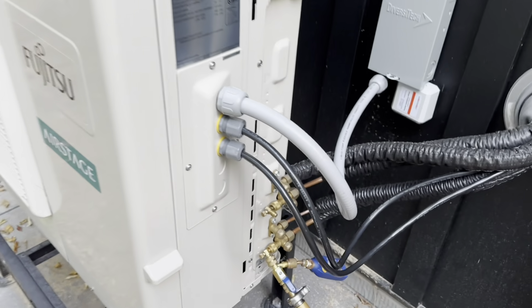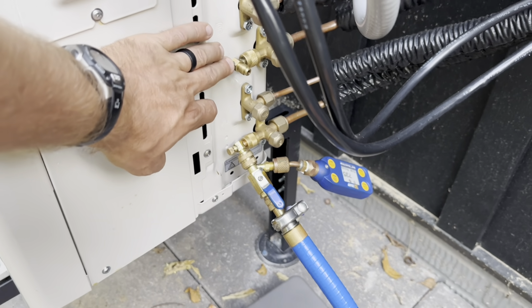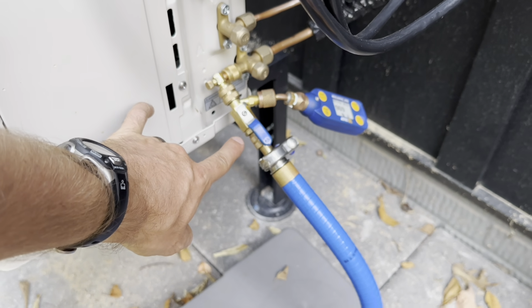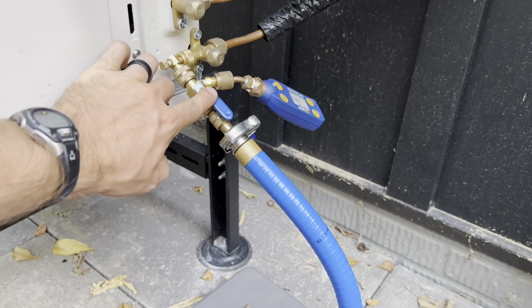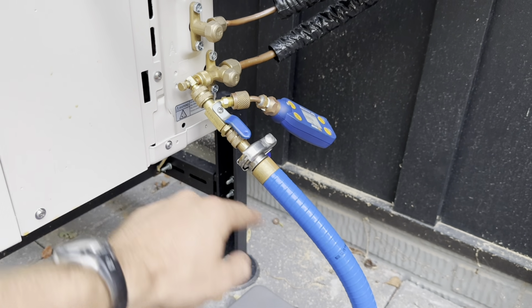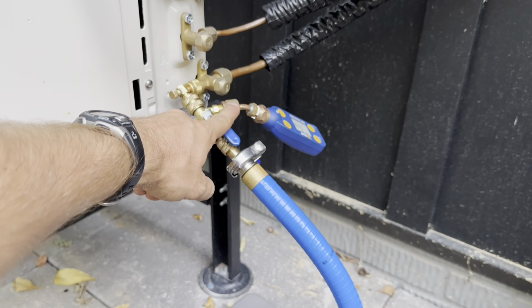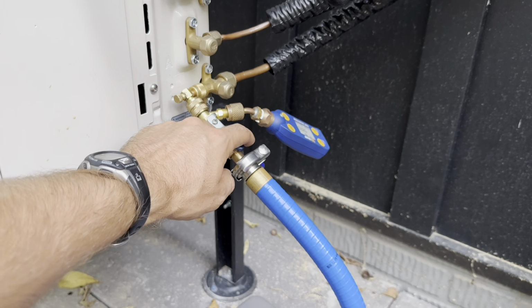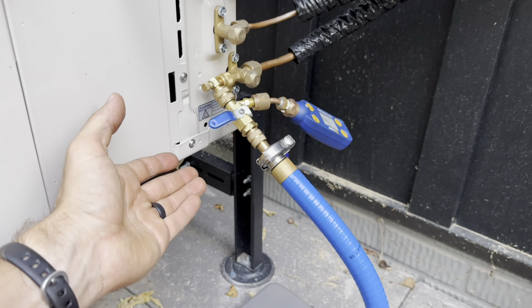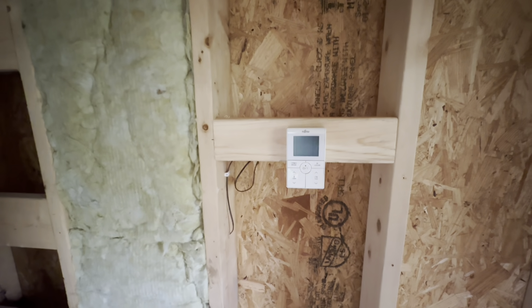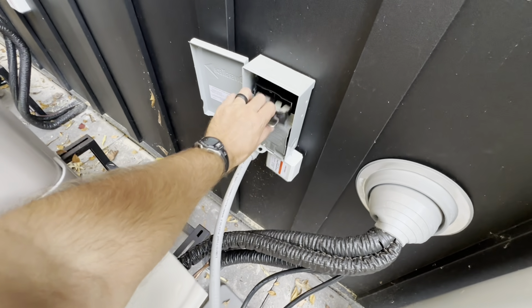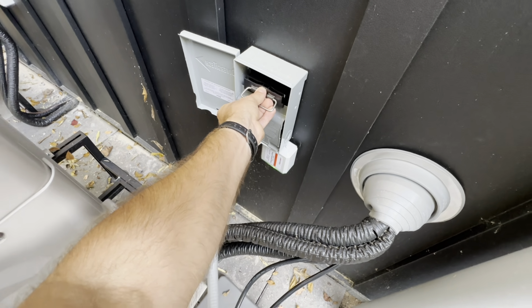Alright, so here's my vacuum setup. Use these angled core depressors with my core remover tool. Vacuum straight in the back, micron gauge on the side, and I can isolate the vacuum just like that. Got the upstairs thermostats temporarily installed so that we can test these bad boys out. There's the one here in the east room and this one here in the west room. Got the power on. Now it's just time to put the disconnect in.